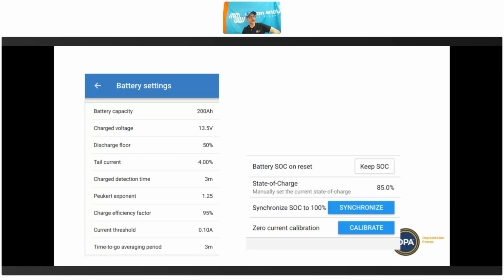The Peukert exponent is just an algorithm for, when I say the battery is 200 amp hours capacity, that's usually at a certain rate of discharge, say C10. And so that means over 10 hours, you would get 200 amp hours out of it. But over a longer duration of discharge, you would actually get more amp hours out of that battery. In lead acid batteries, that's a really dramatic feature because of the chemistry of them. In lithium batteries, it's not as dramatic. The rate of discharge doesn't affect the amount of available stored energy anywhere near as much. I think it's 1.1 normally for lithium, and then 1.25 for lead acid. But it's not something that you need to stress too much about.